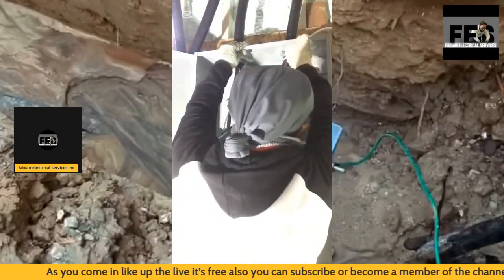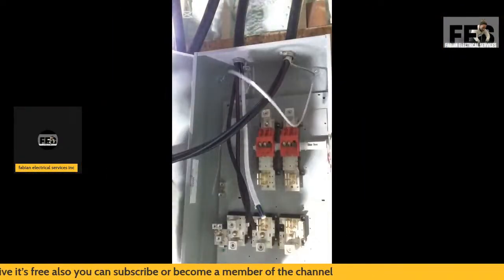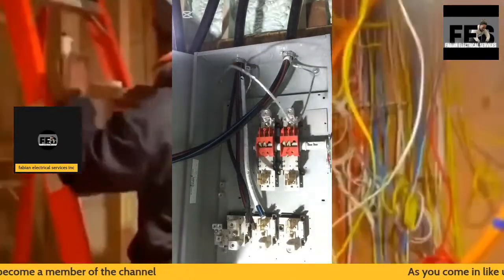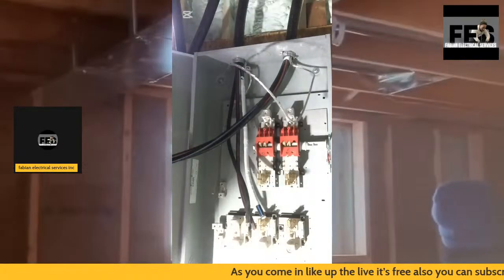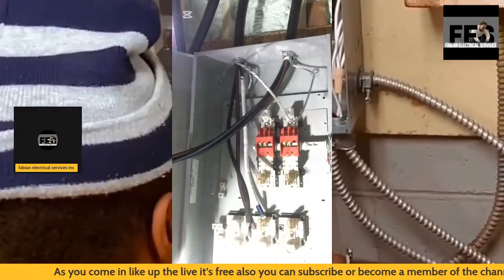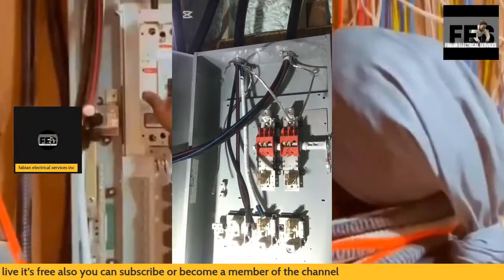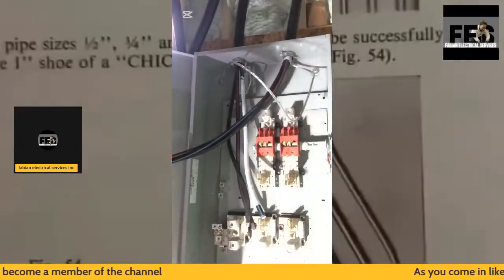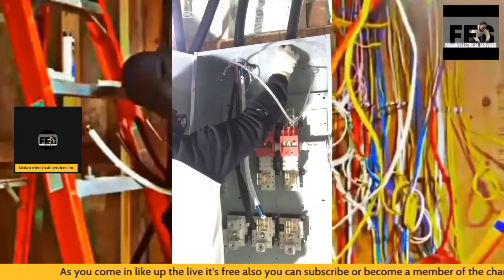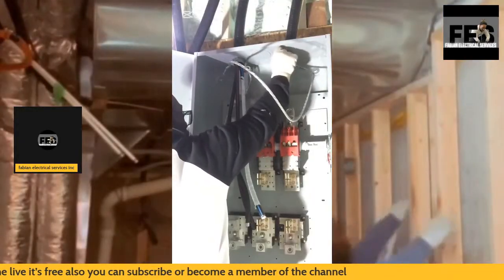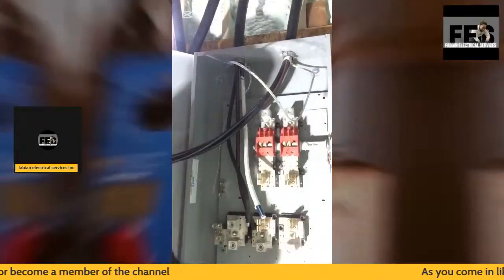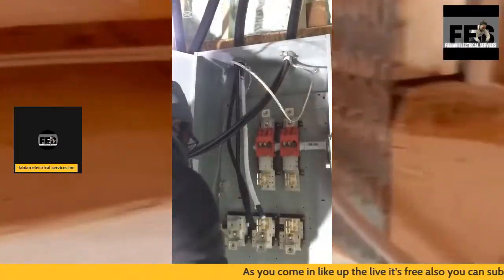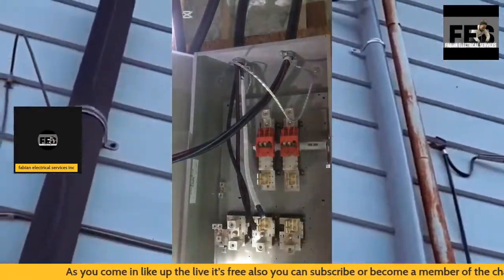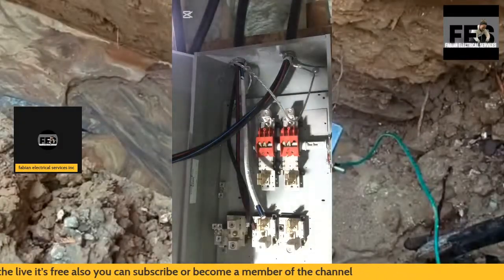Also, you're going to see I have my phasing tape on my cable. The reason is this cable does not come with an identified neutral, and the code book states that your incoming neutral has to be identified. There is an electrical code rule that states that for a particular size of cable we must identify it. So this is what I am doing here, identifying my conductors with the white tape that is being used. It's always best to have your line and loads coming in separated. Never have them touching each other. It is a code compliance rule that states that your main feed coming in is not supposed to come in contact with your actual load side that's going out. So for this reason, you're going to see the installation.